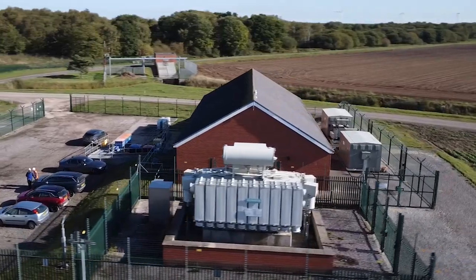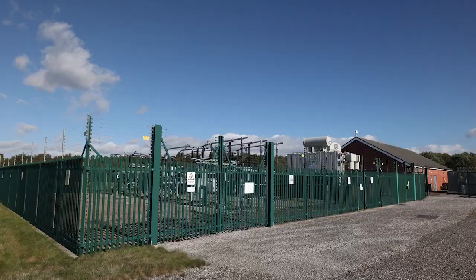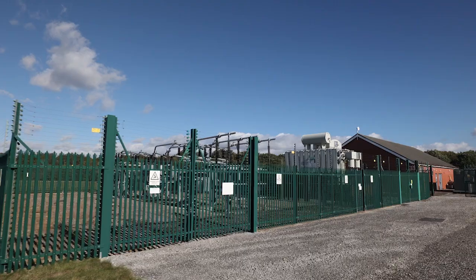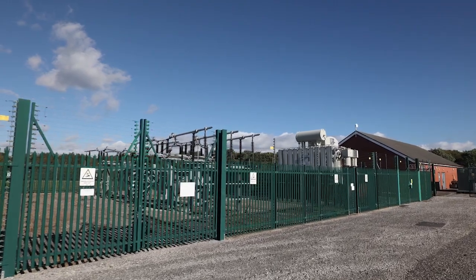Sounds like a lot to remember, but I suppose it comes as second nature to you. A lot of it is common sense. It's not normal to have loads of oil on the floor, so if we spot some, we investigate immediately, as it could indicate a serious and dangerous situation. One thing to remember is that transformers aren't always housed in buildings. We have them in compounds on some of our sites. For instance, on this site there's a large fenced area with a transformer inside.